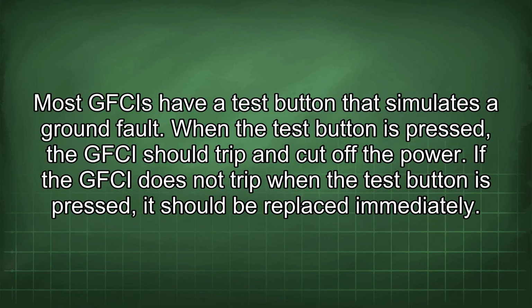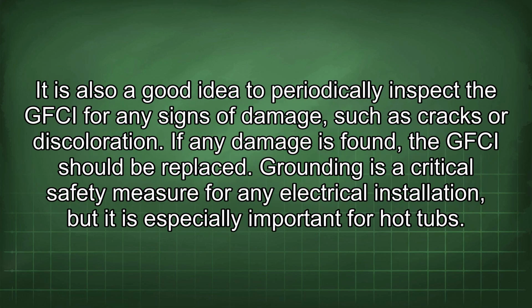Most GFCIs have a test button that simulates a ground fault. When the test button is pressed, the GFCI should trip and cut off the power. If the GFCI does not trip when the test button is pressed, it should be replaced immediately. It is also a good idea to periodically inspect the GFCI for any signs of damage, such as cracks or discoloration. If any damage is found, the GFCI should be replaced.